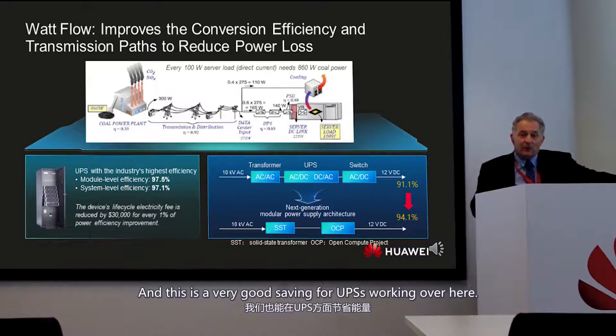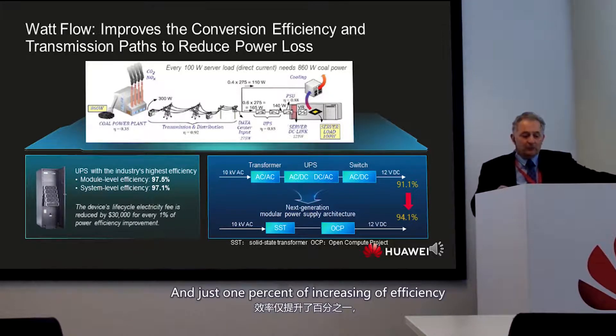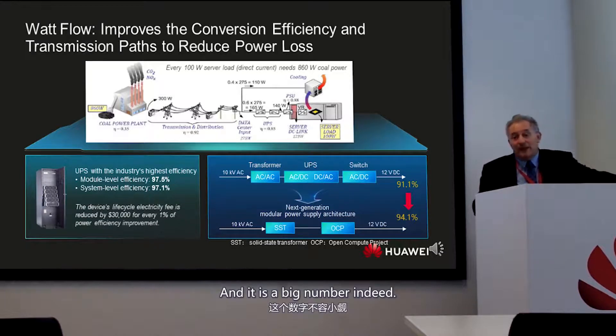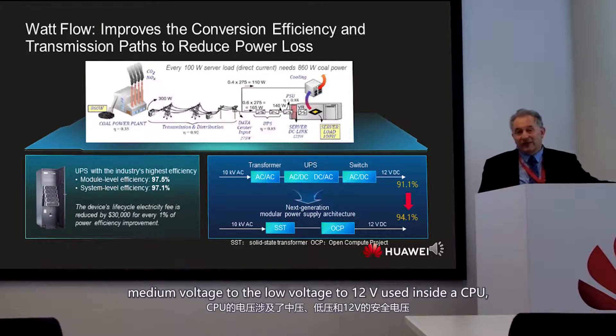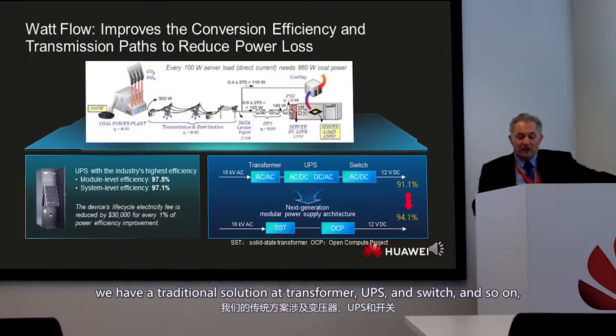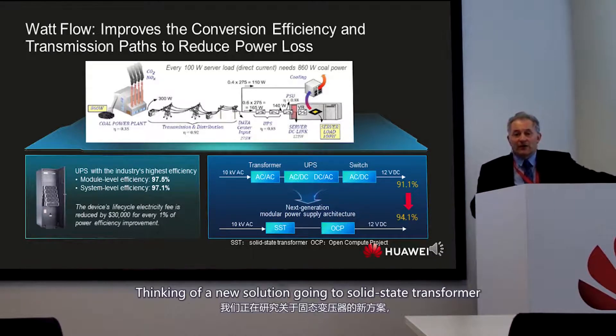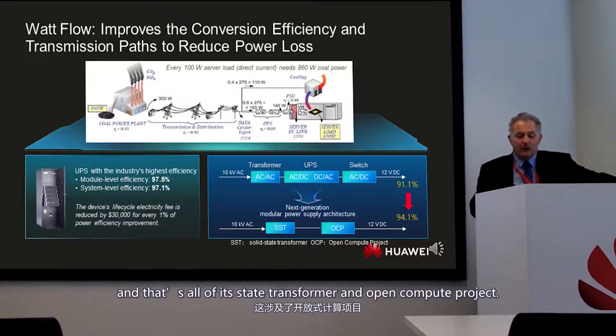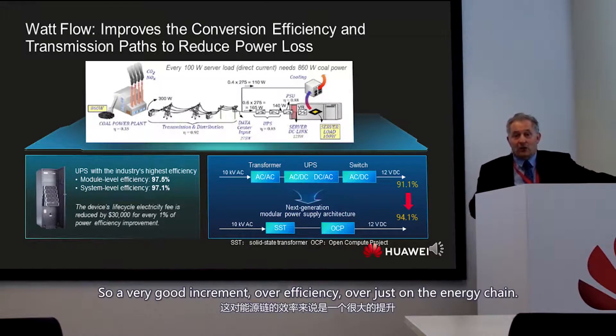This UPS efficiency provides very good savings since UPS systems run all day, all year. Just a 1% increase in efficiency can save around $40,000 per year. Looking at the full power chain inside the data center — from medium voltage down to 12 volts inside the CPU — a traditional solution achieves 91% efficiency. By adopting solid-state transformers and Open Compute Project architectures, we can reach 94% efficiency.